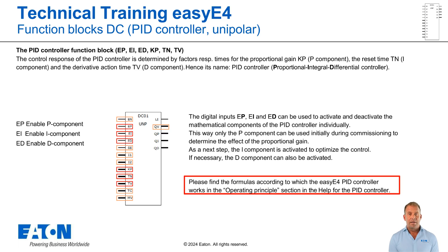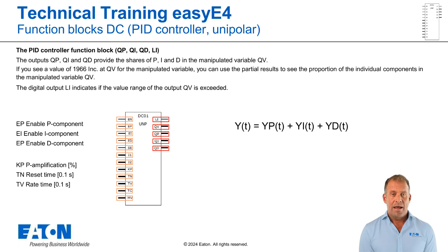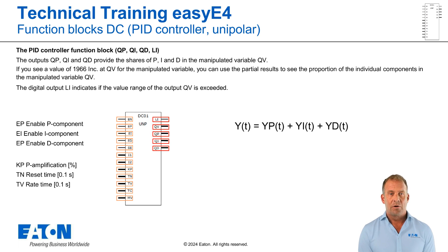The P, I and D components of the control algorithm can be enabled separately by the program using the EP, EI and ED inputs. At the analogue inputs KP, TN and TV, enter the values for the proportional gain, reset time and rate time — these determine the control response. In this way you can switch the parameters on and off individually to commission your control system. The analogue outputs QP, QI and QD provide the values for the P, I and D components of the manipulated variable QV. These values allow the controller settings to be evaluated during commissioning. The sum of all sub-results produces the manipulated variable QV of the PID controller, and these outputs are to be used for diagnostic purposes.